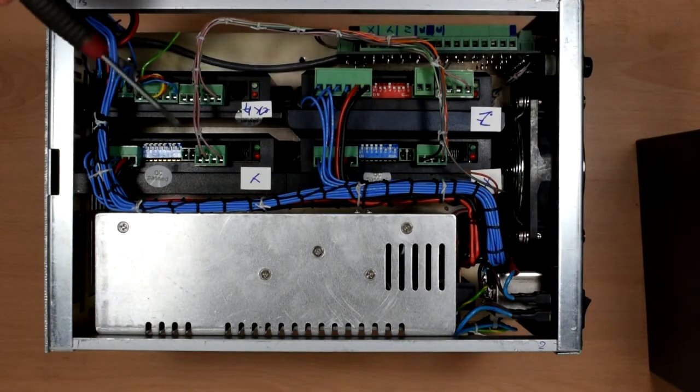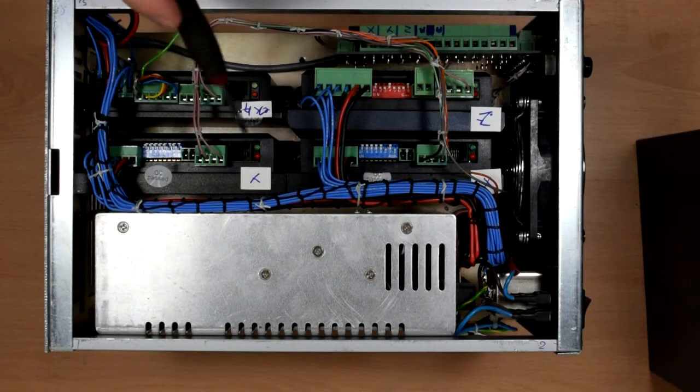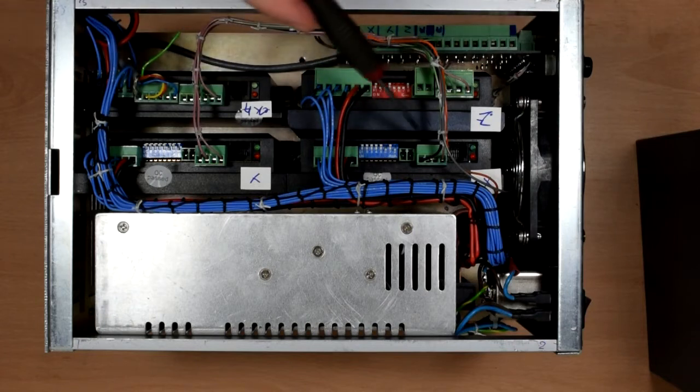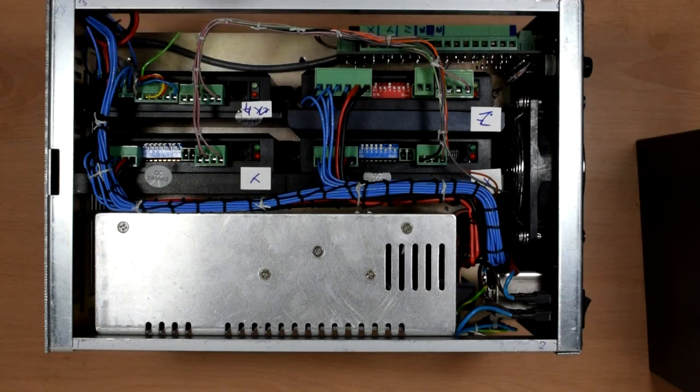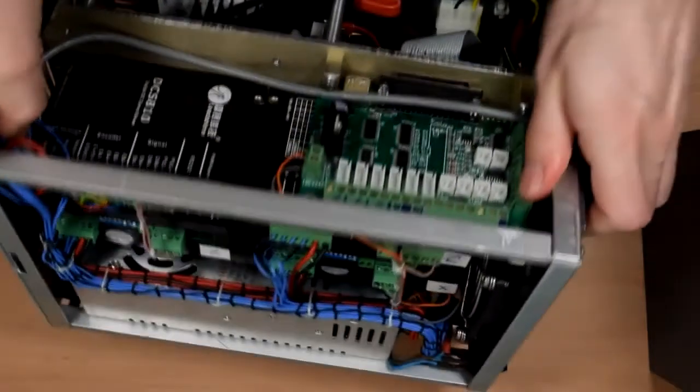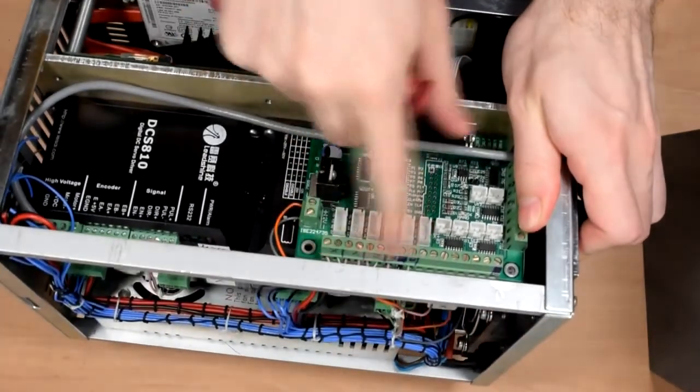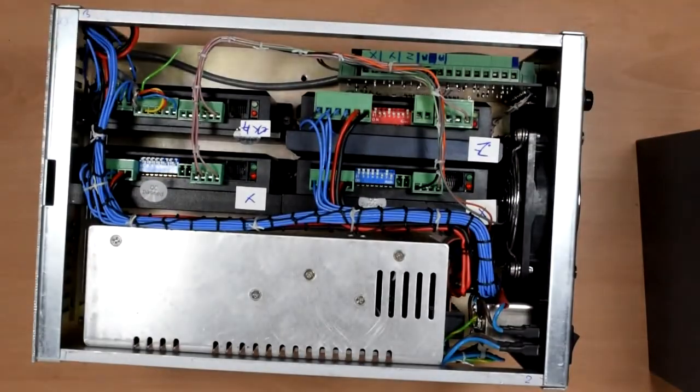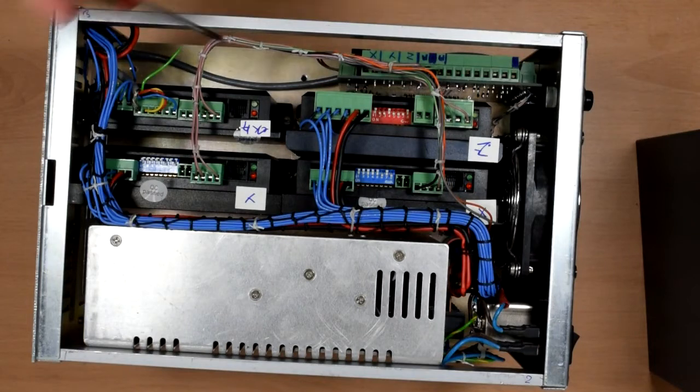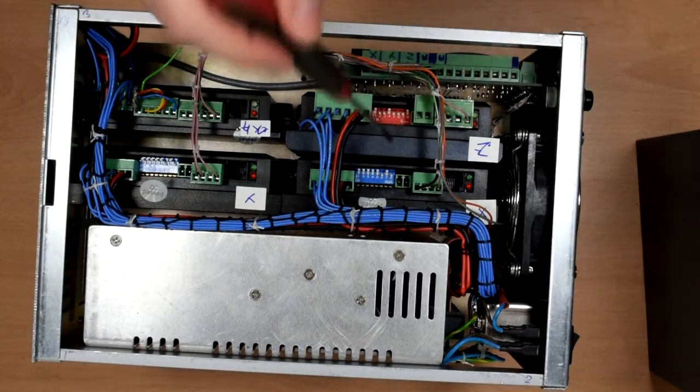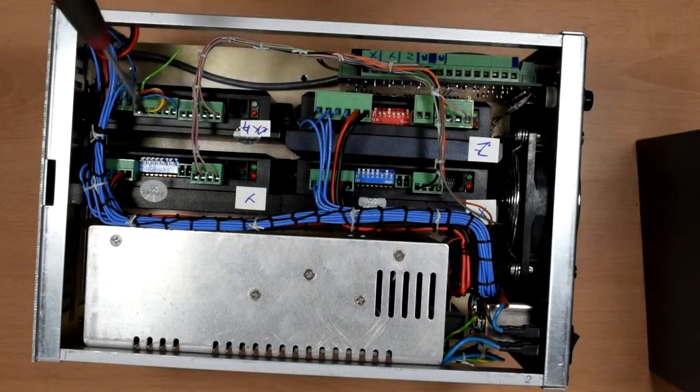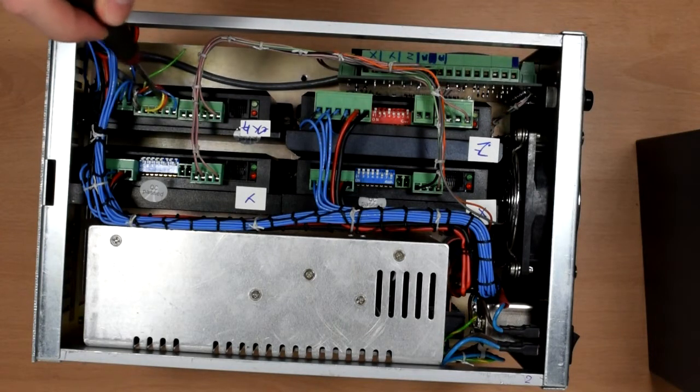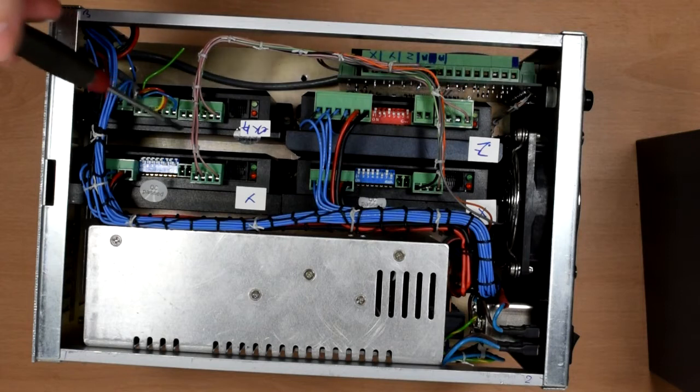So yeah, in fact ideally these controllers take differential inputs, opto-isolated differential inputs, and really seriously consider using that if you're doing anything along these lines. It will help. Unfortunately I can't here because this doesn't have a differential output. So yeah that's kind of rubbish, but seriously differential signaling is there for a reason on these things and it does help and it is needed.